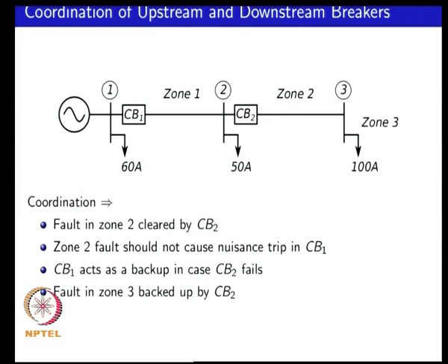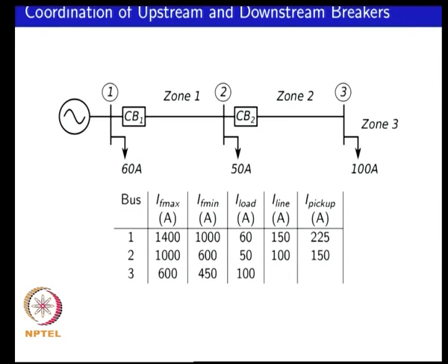We had circuit breaker 1 and 2, and the question was what do you mean by coordinating these two breakers. We discussed the requirements of the individual breakers. The next thing you need for doing the coordination is to perform a fault analysis at the different zones in the bus, identify the range of fault currents expected at the protective device, the nominal current, and then decide on what parameters to apply to your breaker to enable appropriate coordination.